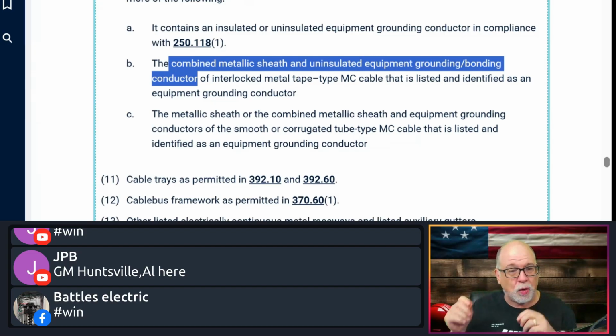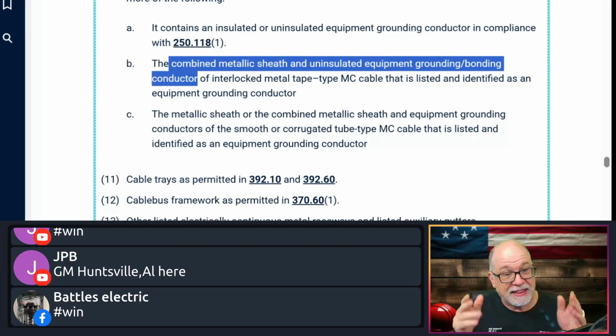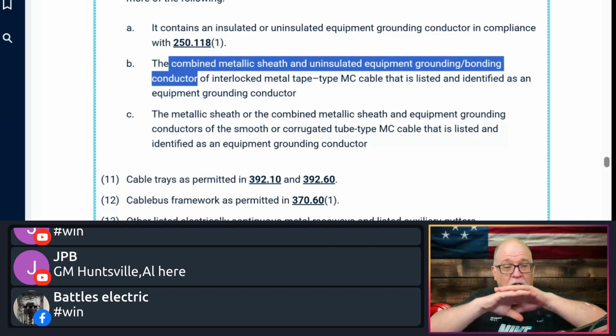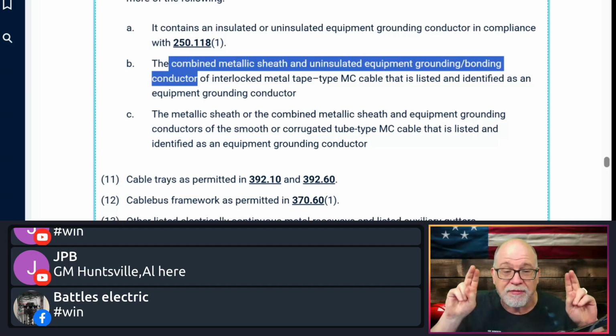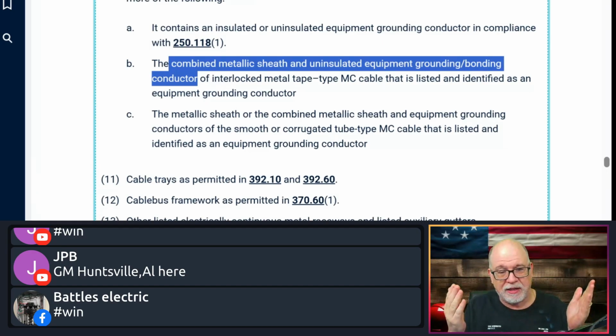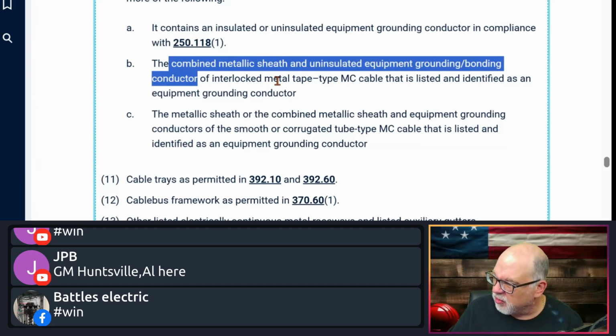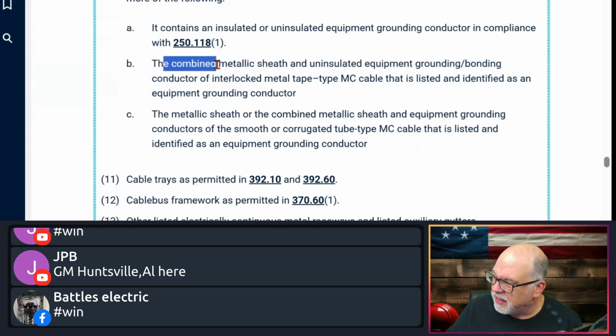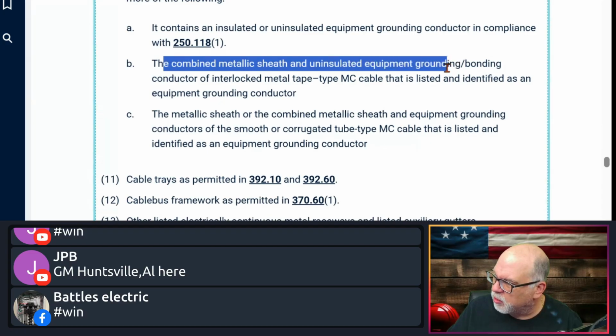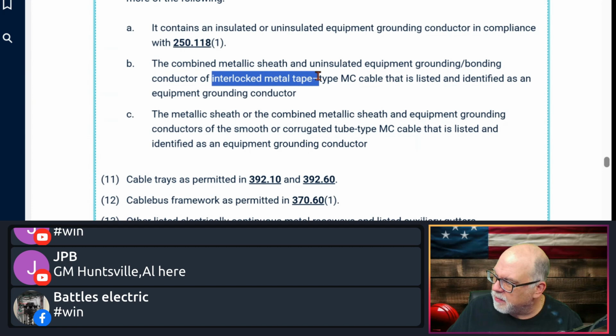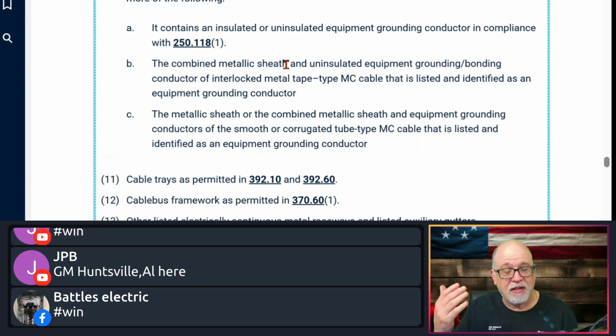That is not an equipment grounding conductor. But that grounding/bonding conductor makes the armor qualify as an equipment grounding conductor. Why? Because it says right here, the combination of the metallic sheathing and uninsulated equipment grounding/bonding conductor of interlocked metal tape type MC cable that is listed and identified as an equipment grounding conductor. That is your MC cable.